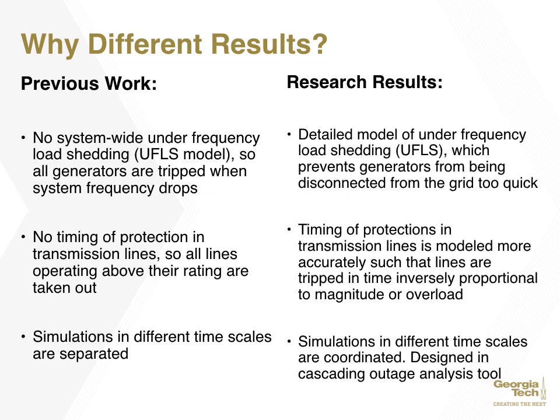It has to be mentioned that the topic of MadIoT attacks has been researched before, but this paper reaches a different conclusion, for reasons that can be summarized as such. In previous research, there is no system-wide under-frequency load shedding, and this UFLS model will be discussed later in this presentation, meaning all generators were tripped when the system frequency dropped. There was also no timing of protection in transmission lines, so all lines operating above rating are also taken out. Finally, simulations in different timescales were separated.